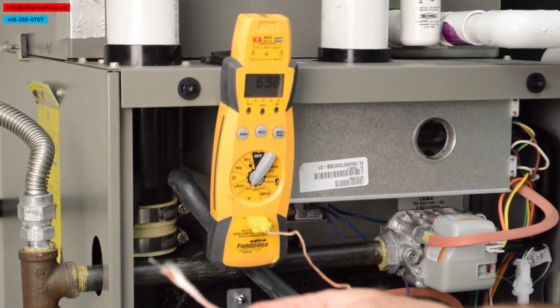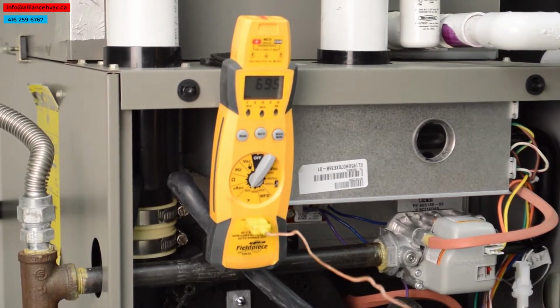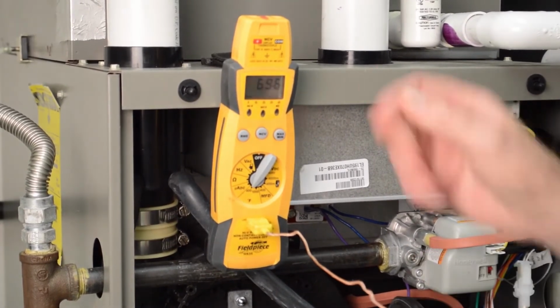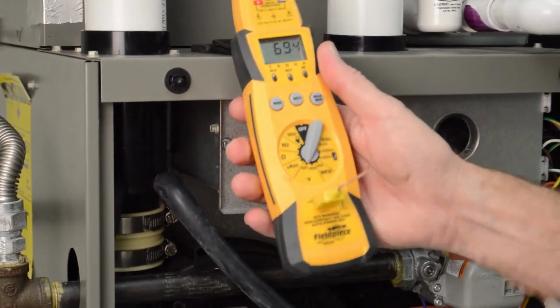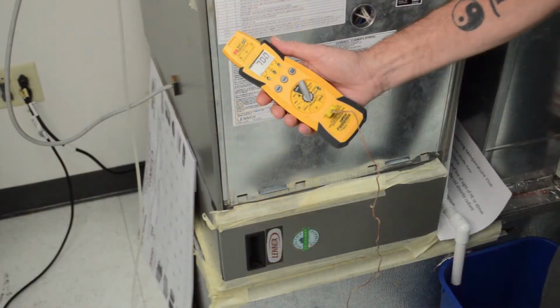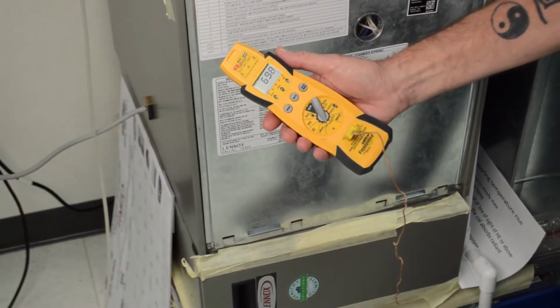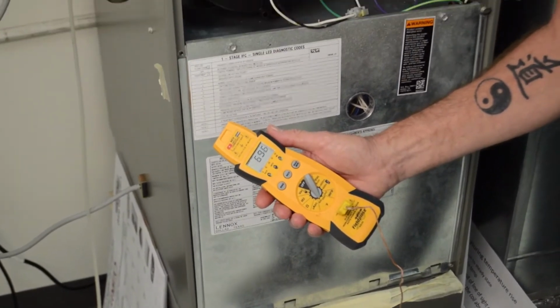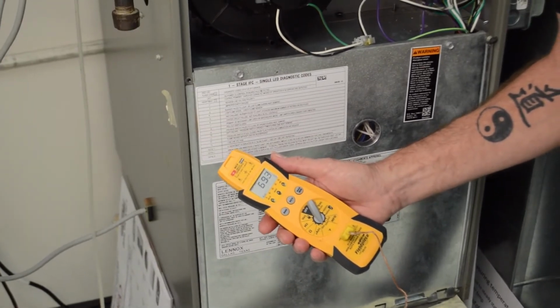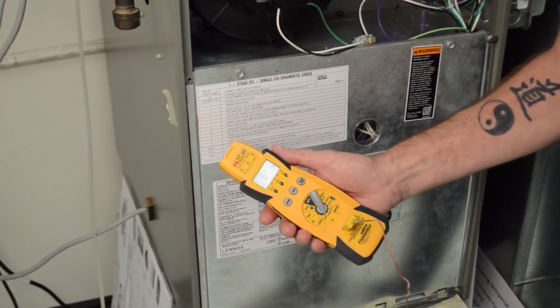The furnace is going to be in a steady state efficiency. In other words, it's going to be operating for 15 to 20 minutes to make sure it is up to full temperature. On the return side, out of line of sight of the heat exchanger, we're just going to measure the temperature. This is going to be the return air temperature coming into the furnace. Okay, it's about 69 degrees, 69.3 degrees.